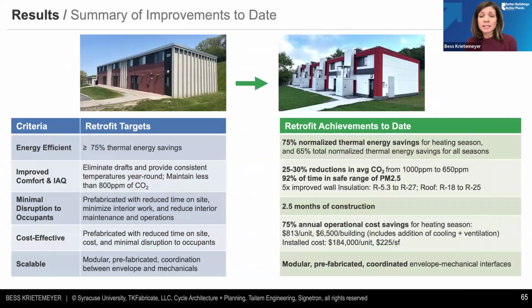Overall, we're really proud of this effort. Our team has done a tremendous job. We are meeting our retrofit goals in a lot of ways. We're seeing that 75% thermal energy savings during the heating season, also providing continuous ventilation, which is new. We're seeing 20 to 30% reductions in average CO2, with over 90% of the time the air is in the safe range for particulate matter.